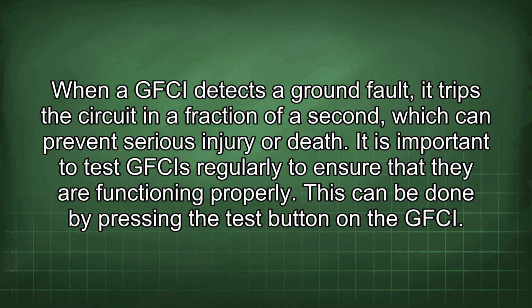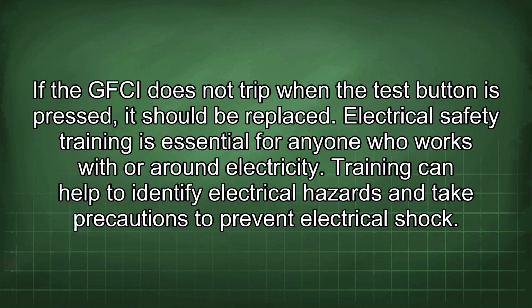When a GFCI detects a ground fault, it trips the circuit in a fraction of a second, which can prevent serious injury or death. It is important to test GFCIs regularly to ensure that they are functioning properly. This can be done by pressing the test button on the GFCI. If the GFCI does not trip when the test button is pressed, it should be replaced.